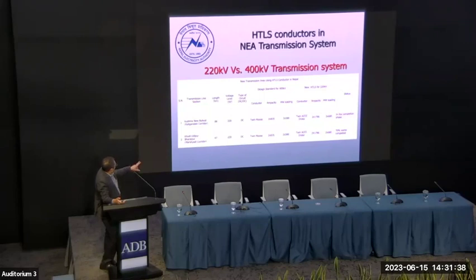For a normal 400 kV line, we did extensive studies - stability studies, load flow studies, and cost analysis - to decide whether to use twin moose conductor at 400 kV or HTLS conductor at 220 kV. After long studies, we chose these corridors with 220 kV HTLS conductor.